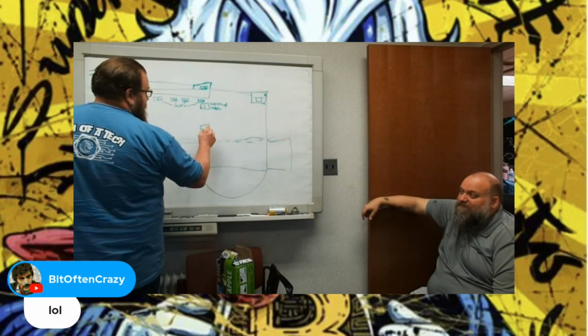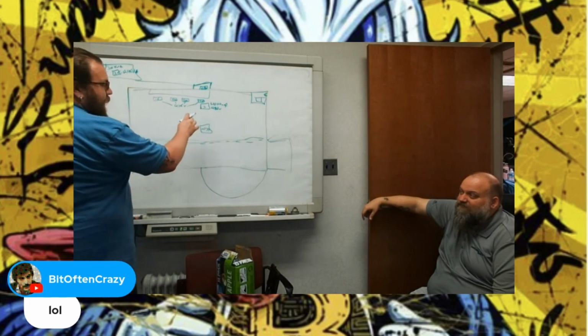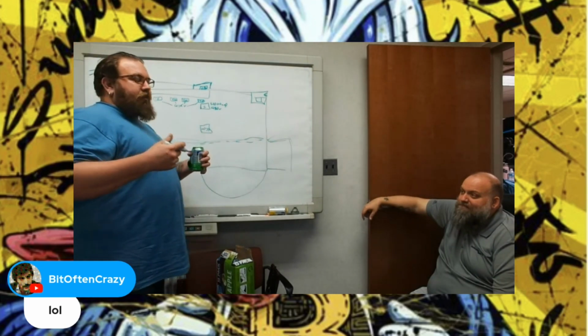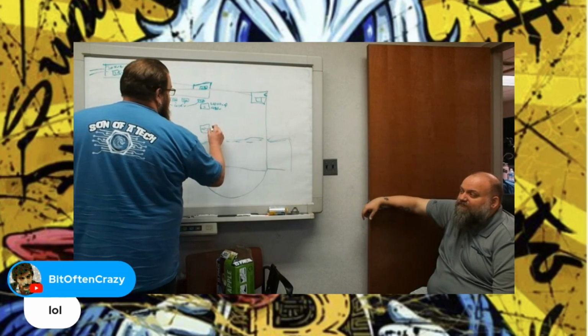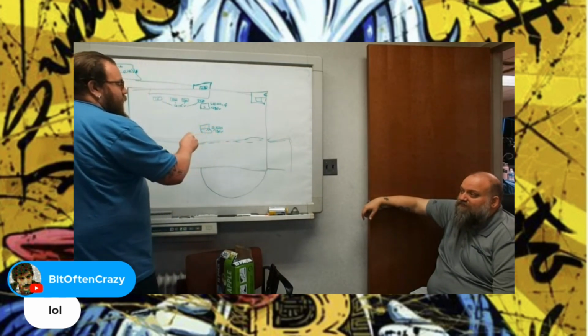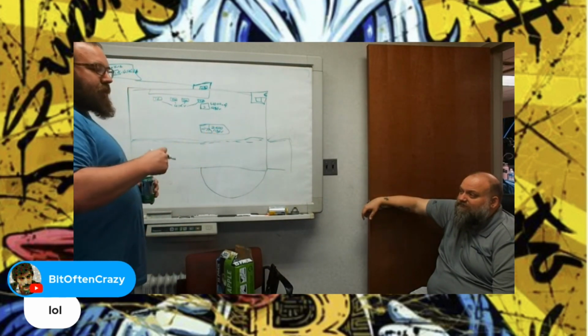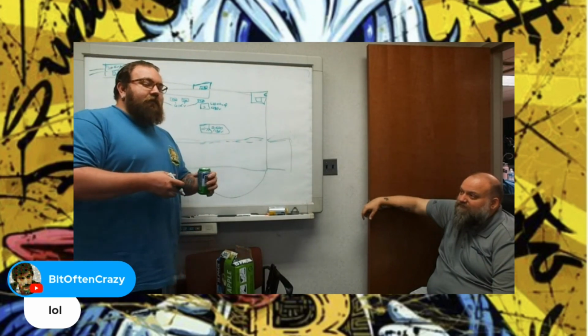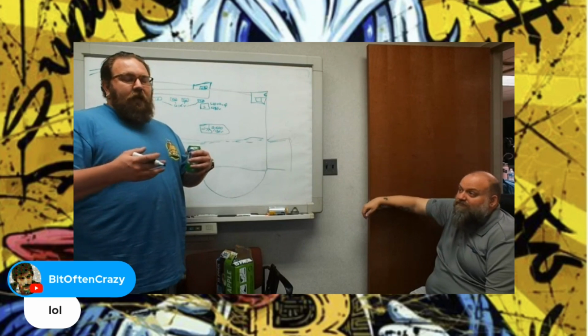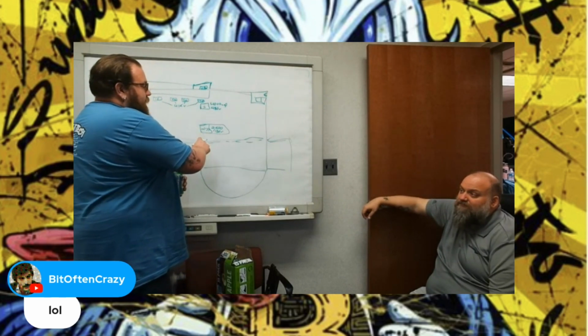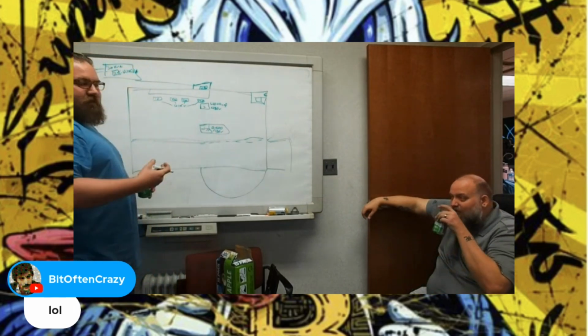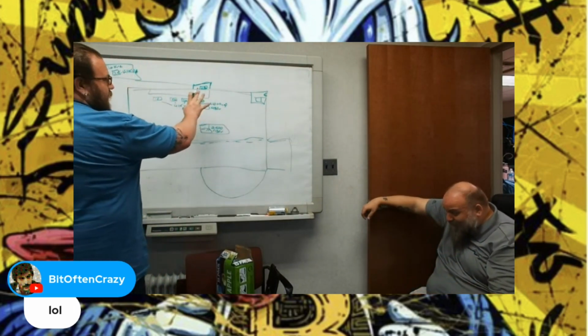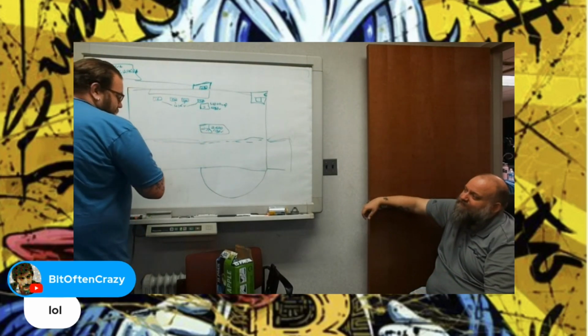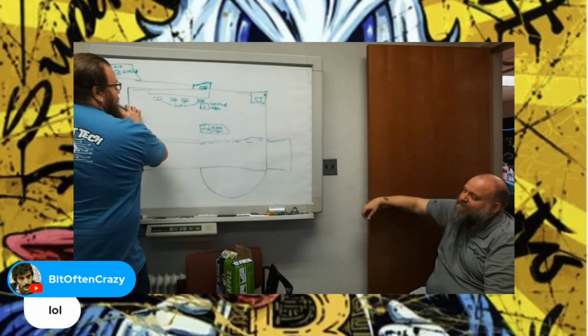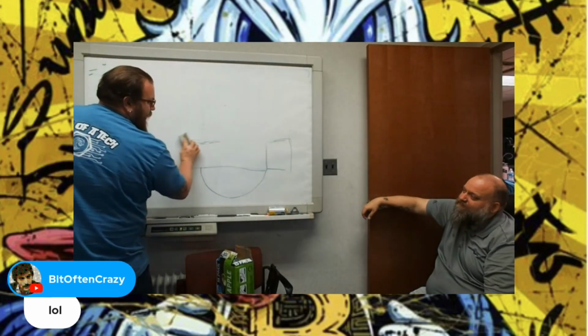Our second build out on this side is our 277 mezzanine. We call it 277, but it is a 3500 kVA 480 transformer that is on this mezzanine. And we're able to pull and separate those 480 lines down to 277 to run all the new generation machines. There's no step down transformers needed. That's why we can build out this 277 a lot faster than we can the 415 step downs. So that consists of our current high bay scenario. I'm gonna erase this, I'm sorry, and I'm gonna draw the low bay a little bit larger because there's a lot more going on in the low bay.